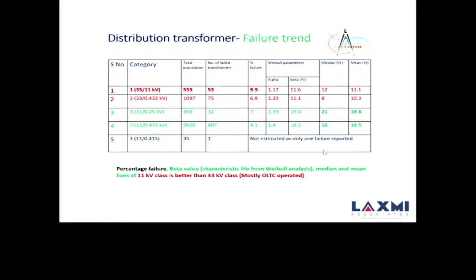Then we did some failure trend analysis rating wise, and we find that 33/11 kV transformers not having OLTC have a lower failure rate, and those having OLTC at 33 kV have a higher failure rate. That is what you see here: this is 9.9 and 6.8, and this is the lower failure rate. In the alpha-beta study we did, we find that the median life is also less for those transformers, 12 and 8, and where the life is more.